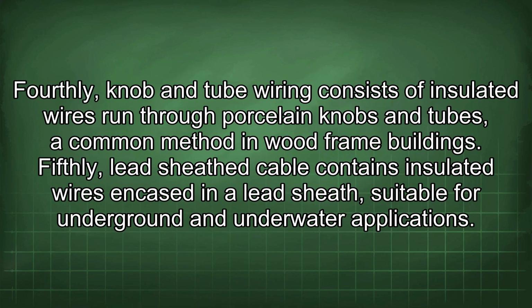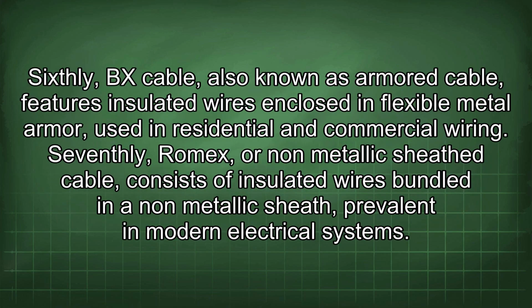Fourthly, knob and tube wiring consists of insulated wires run through porcelain knobs and tubes, a common method in wood frame buildings. Fifthly, lead sheath cable contains insulated wires encased in a lead sheath, suitable for underground and underwater applications. Sixthly, BX cable, also known as armored cable, features insulated wires enclosed in flexible metal armor, used in residential and commercial wiring.